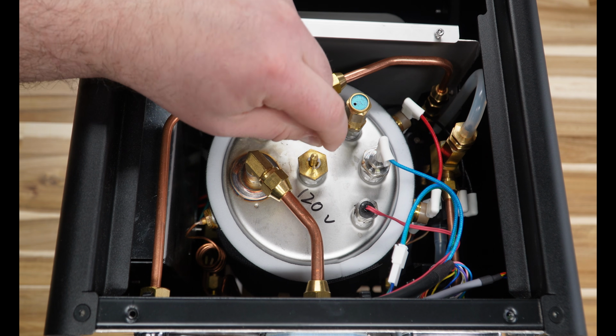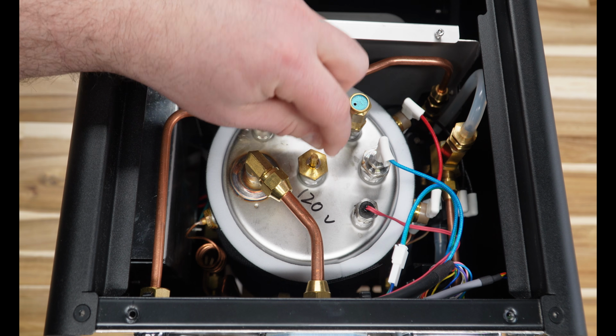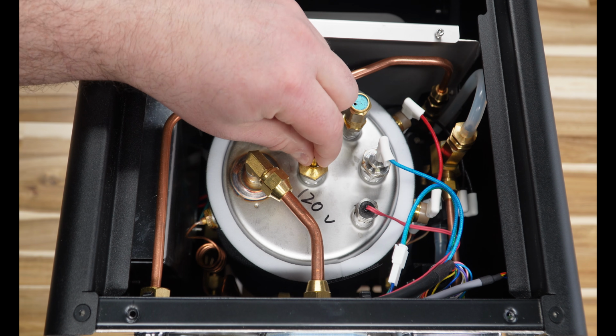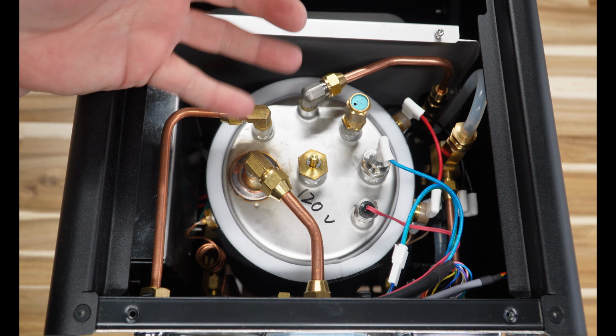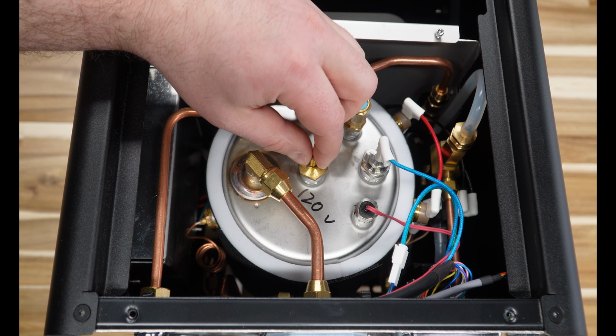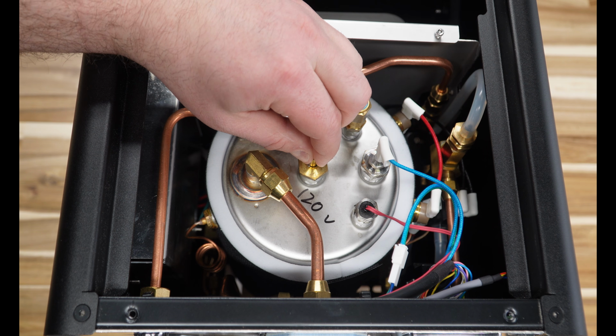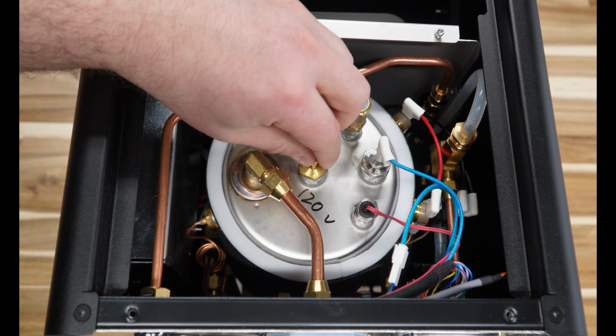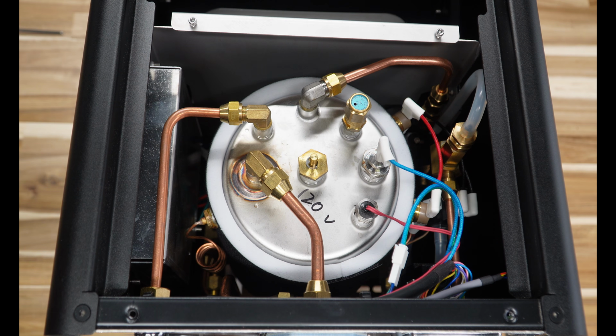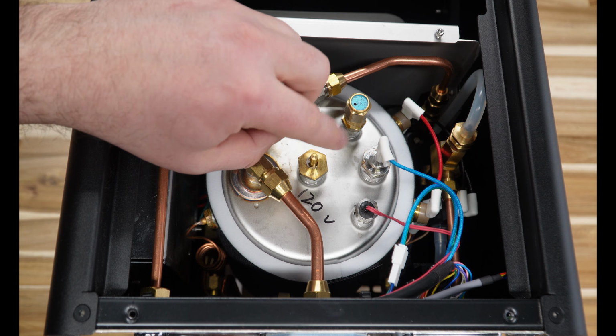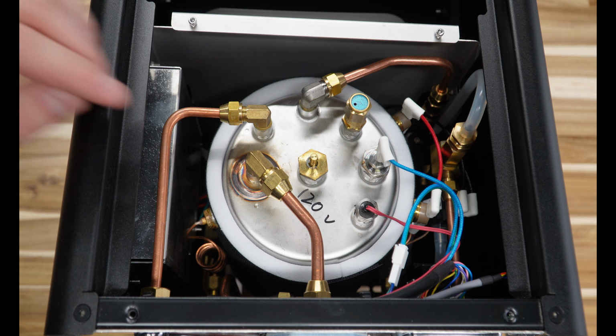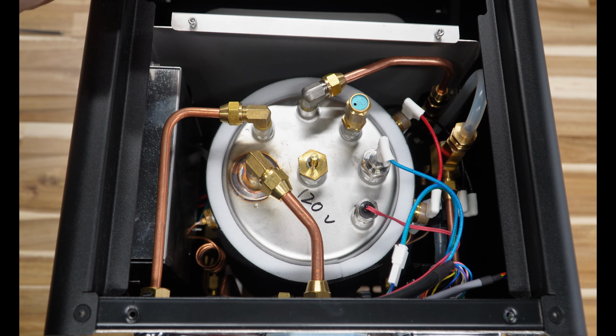In the middle we have our anti-vac, and you can see it just moves around. When our boiler begins to pressurize, it pops up and will clog up that port. And when it cools down, it releases the vacuum pressure inside the tank. Sometimes you'll have issues with machines that don't have these. I think almost everything nowadays does, but it's nice and easily accessible on the top.